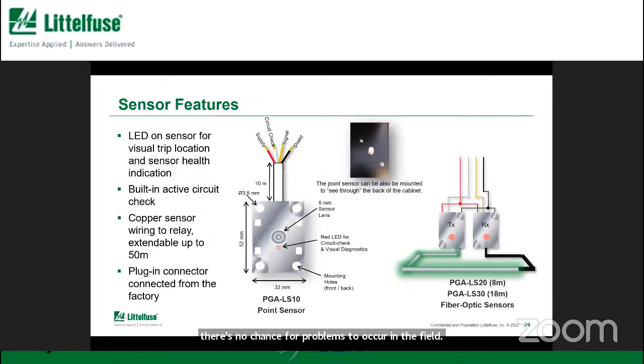Now I mentioned the self-check. So both of these sensors have an interesting self-check. In this single point sensor here on the left, there is a red LED inside the body. And when you plug it into the relay, that LED will flash. And that light from the LED is actually picked up by the sensor. And then the sensor transmits that to the relay and confirms we have a correct test signal. So that's verifying the circuit, and that's verifying the cable as well. So if there's any cut in the cable, the relay would know instantly that this is not working.